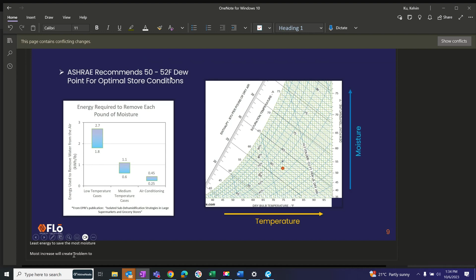Yeah, it freezes up their coils. So their coils are running at just above freezing, and I'm sorry, I had to relearn Fahrenheit. I mean, I'm a Canadian. Naturally, I think Celsius, but I've had to relearn Fahrenheit in this industry. So they're running their temperature to those cases at like 35 Fahrenheit, just above freezing for their dairy and meat. And then their frozen goods are minus 20 kind of range. Their coils are even colder, of course, to create that environment. And so, as you can imagine, at a 50-degree dew point, those coils are always going to see moisture condensing on them. If it's higher, it just gets worse.